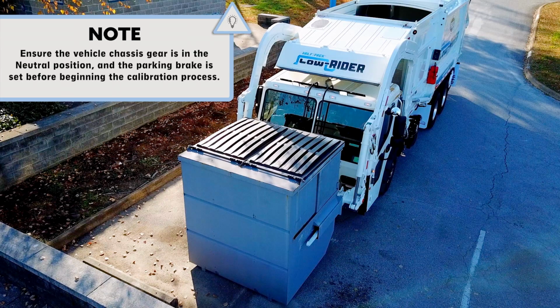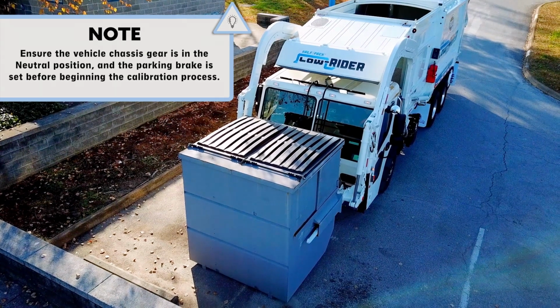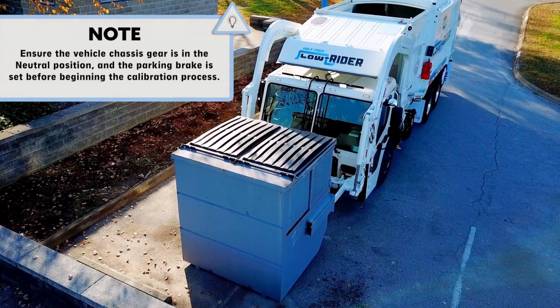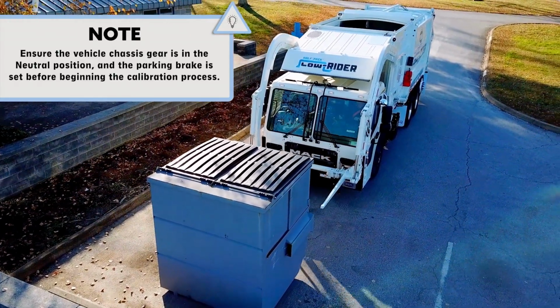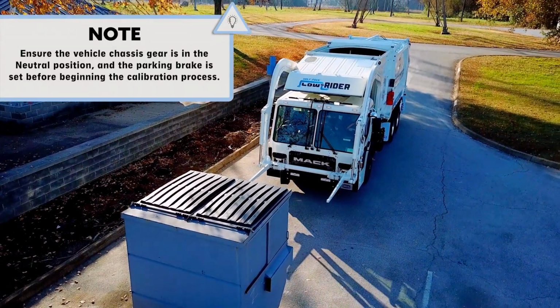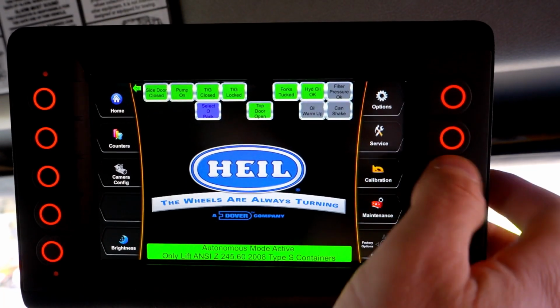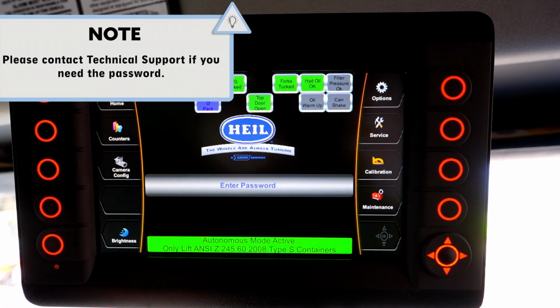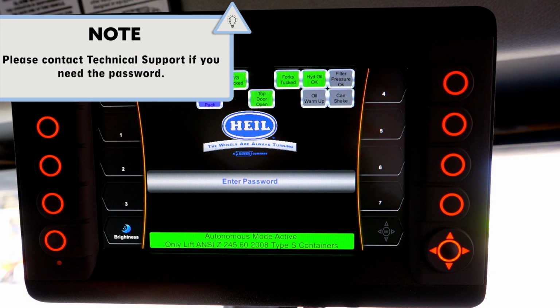First, remove any containers or objects from the forks completely. This is a critical first step. Calibration cannot be completed with anything on the forks, and damage will occur during calibration. Once you have ensured the forks and arms are in an area where there are no surrounding obstructions, press the calibration button on the monitor, and then the message "Enter Password" will appear. Enter the password and press the OK button.